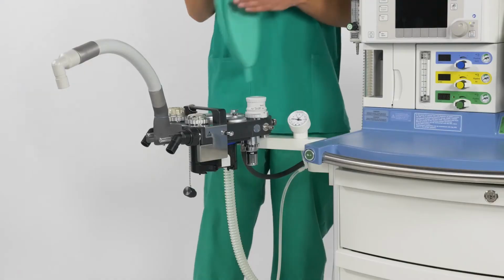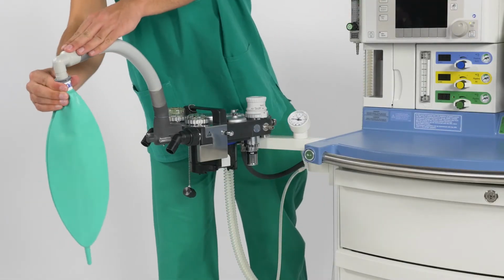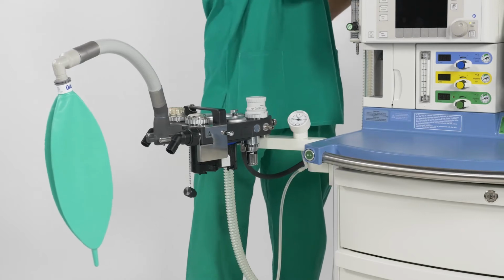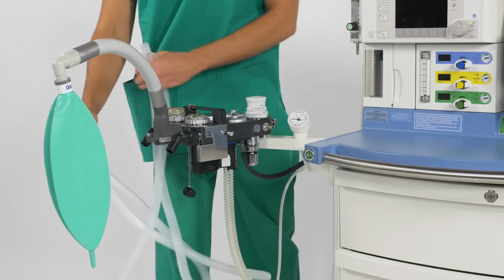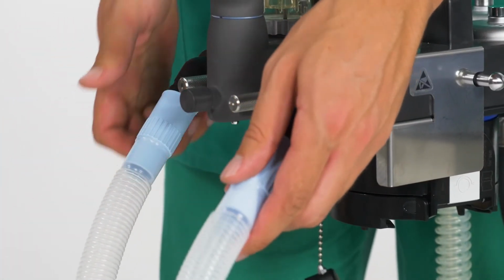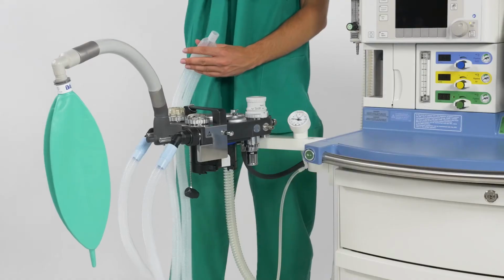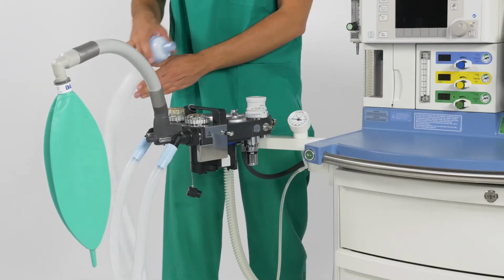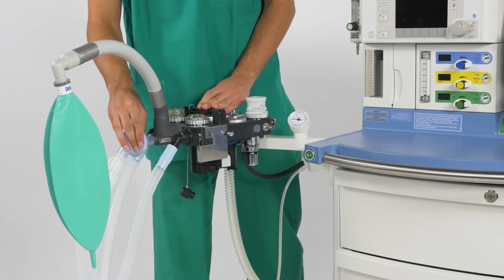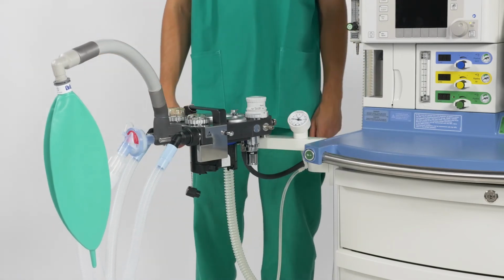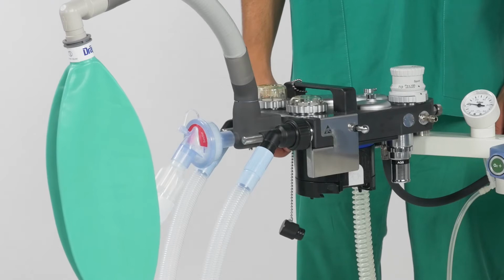Connect the breathing bag and the patient breathing hoses to the breathing bag, inspiratory hose and expiratory hose ports on the COSY. All filters that will be used during operation should be installed as well, in order to include them into the self-test. In this case, we will use a filter on the Y-piece for demonstration purposes. Place the filter on the park position on the breathing bag port of the COSY.